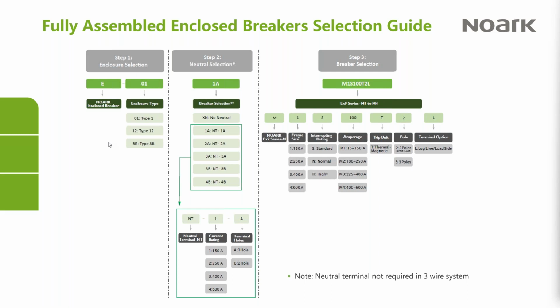Interrupting rating, so standard, normal, and high interrupting ratings. The literature for the product has all of the interrupting ratings listed in it. Then of course you're going to select a specific amp rating of the breaker. In this case, all of the trips are thermomagnetic. Once we introduce the 1200 amp, we'll have an electronic trip in there as well. And then the number of poles, is it 2-pole or 3-pole? And then the last digit is always the same, meaning that the breaker comes with lugs included.